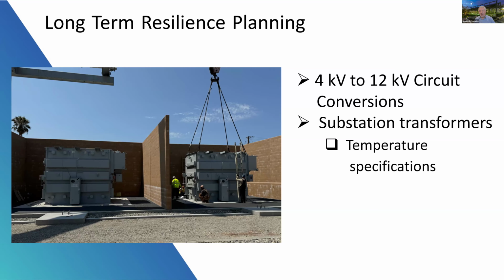Those substation transformers are obviously a critical component in our electrical substations. Burbank Water and Power is saying lead times go from less than 1 year to 4 years right now for substation transformers, which causes us a lot of concerns, and we obviously want to make sure that those transformers are as reliable as possible. So in 2021, we had a project where we had to review our temperature specifications to replace a couple of transformers, and I'll go in further as to what we discovered there. Next slide, please.